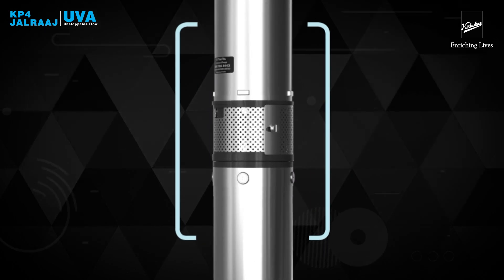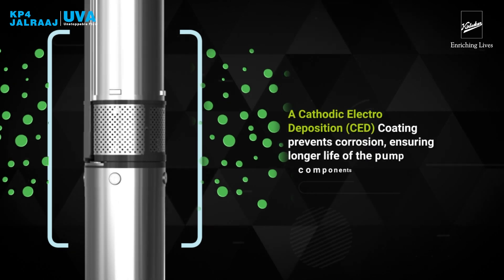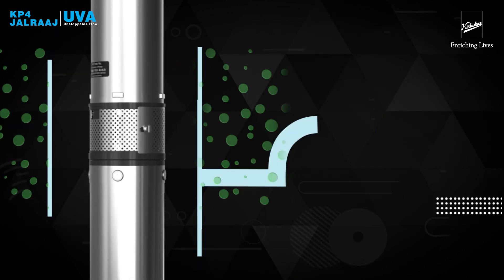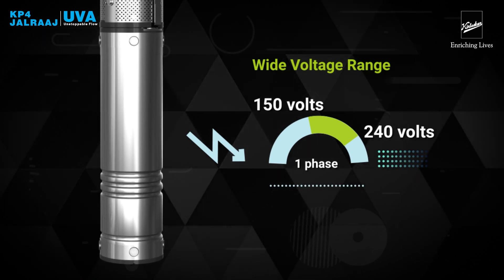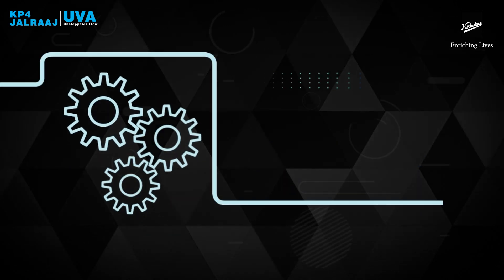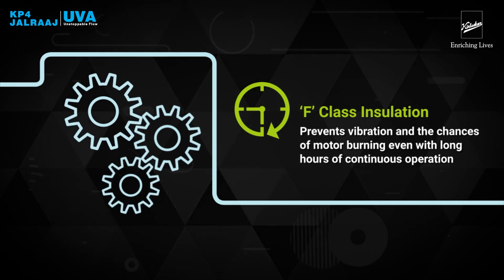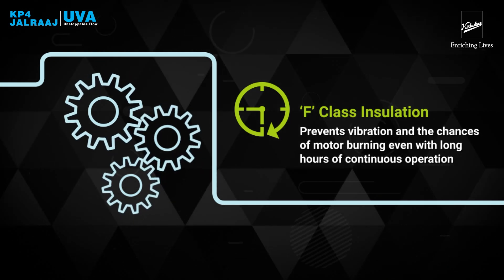A cathodic electro-deposition or CED coating prevents corrosion, ensuring longer life of the pump components. The wide-voltage motor design helps UVA perform well within a wide voltage band of 150V to 240V for single phase without any fear of motor burning due to voltage fluctuation. Motor with dynamically balanced rotor parts and superior F-class insulation prevents vibration and the chances of motor burning, even with long hours of continuous operation.